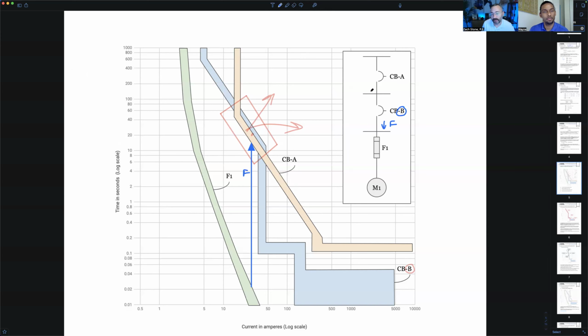We don't want A to trip because this is a single line diagram, right? But we're assuming this is a big bus. We're assuming we've got more breakers being fed from circuit breaker A, to where if circuit breaker A trips, not only do we lose B, but we also lose any other breakers on this bus, right? So we only want circuit breaker B to trip for this fault right here. Make sense? It does. Yes.